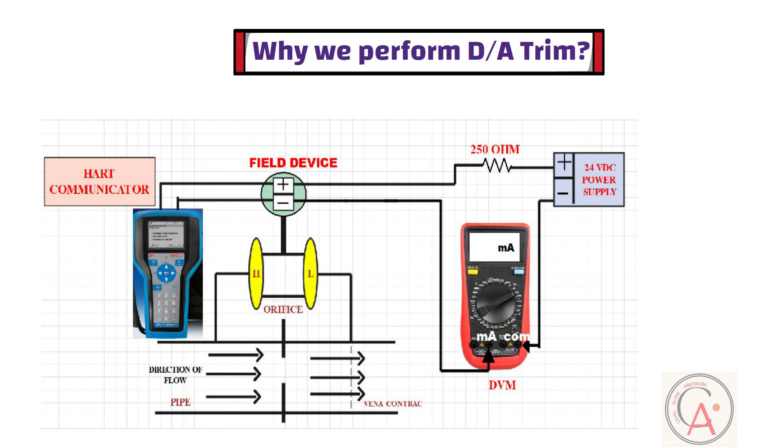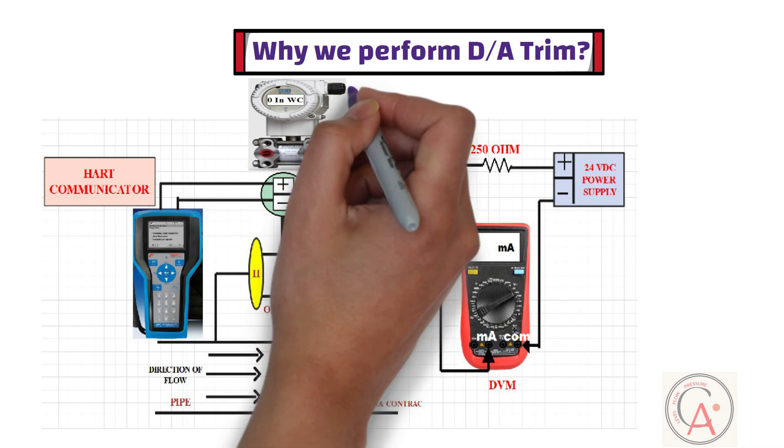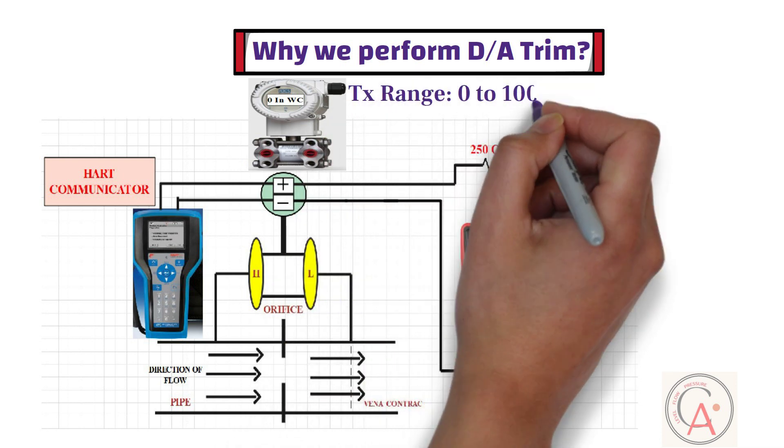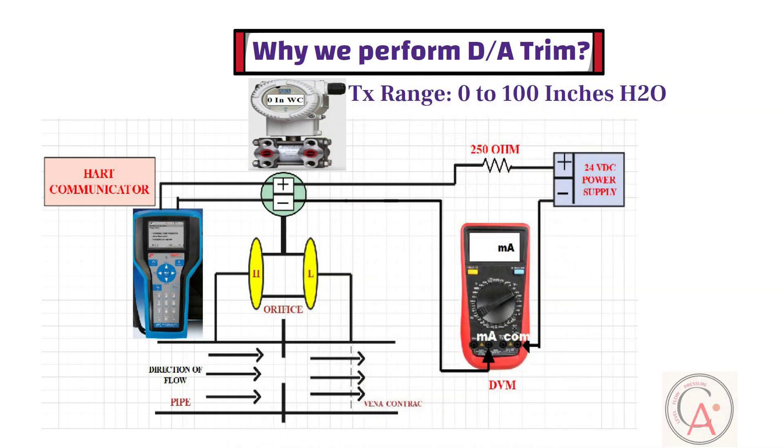Digital to analog trim needs to be performed when analog output value of transmitter is out of specified range. For example, if transmitter's range is 0 to 100 inches of H2O, and if transmitter gives 4.286 milliampere at 0 inches H2O pressure. In this case, digital to analog trim will be required to set milliampere output at 4 milliampere.